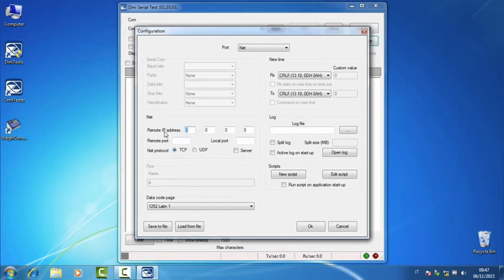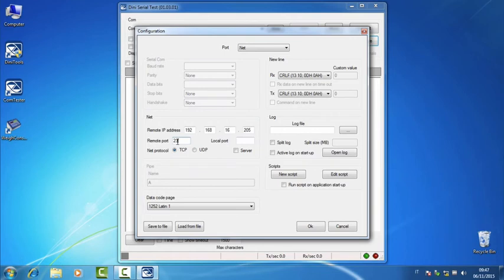We click on Configure. We select the port Net. We set the address of the Ethernet card of the indicator, so 192.168.16.205, and the remote port for our serial port is 23. You can change if necessary using the programming browser we have seen before. We confirm with OK.